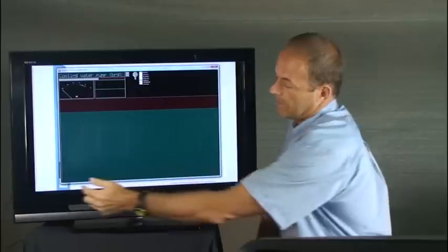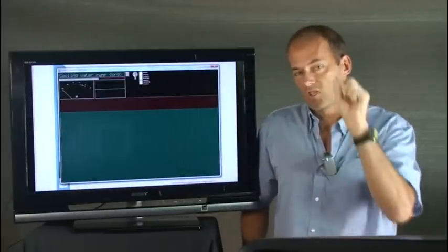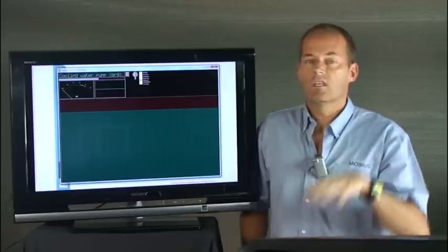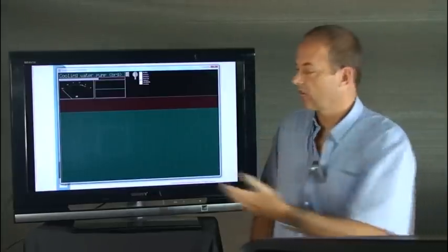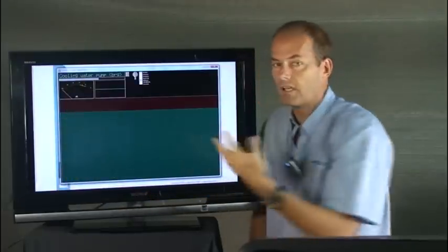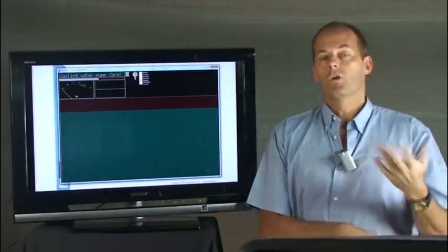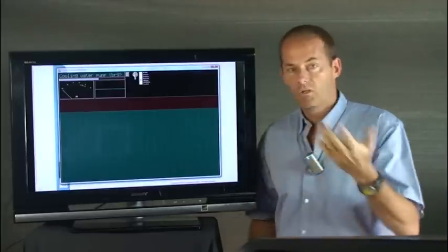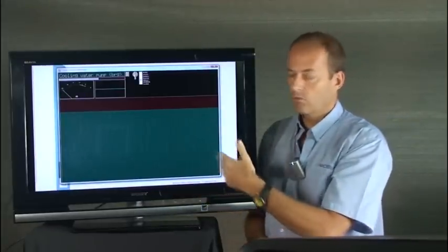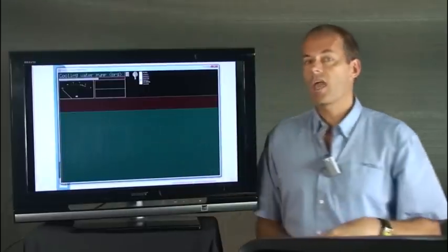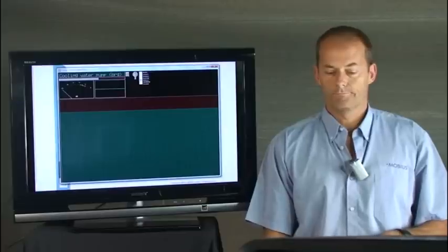And it's designed to basically allow all the vibration through of interest to us, but just block out the very low frequencies, which can be affected by the integration process. So the integration process will generate a lot of really low frequency vibration, so the high pass filter blocks that out. We also use high pass filters when we're looking at demodulation and enveloping. We allow all the bearing frequencies through and block out all the really high amplitude, low frequency signals.